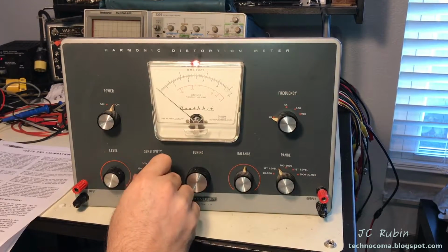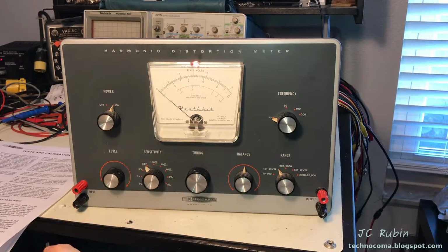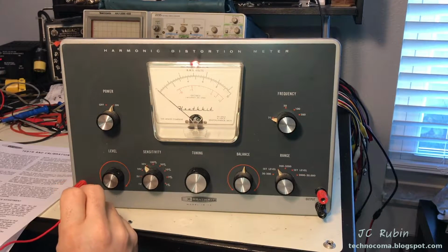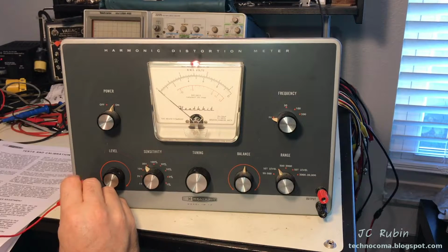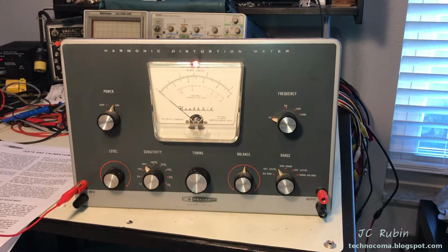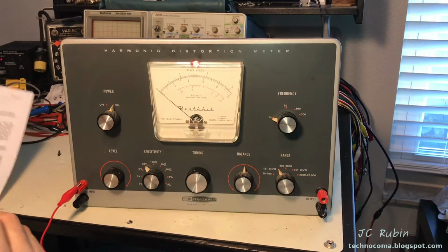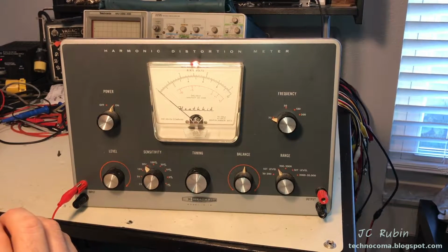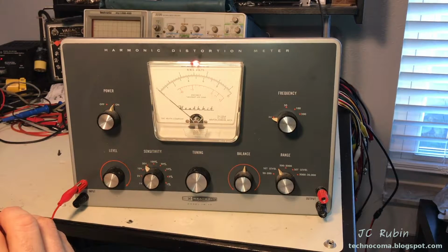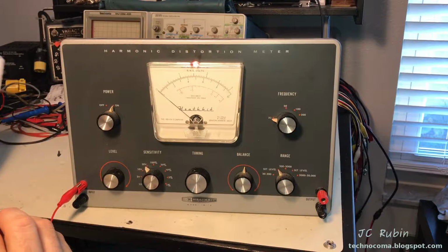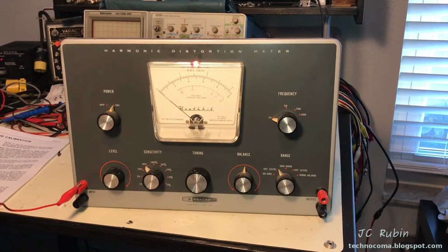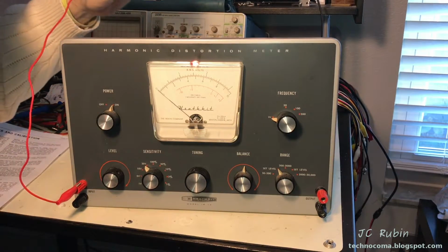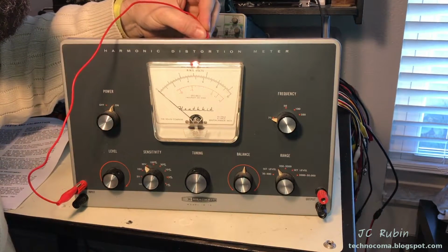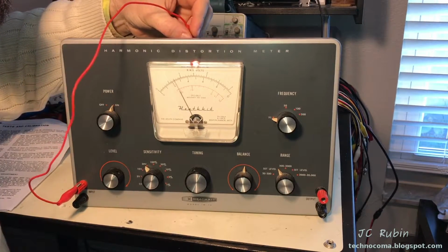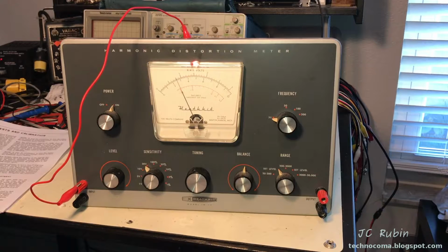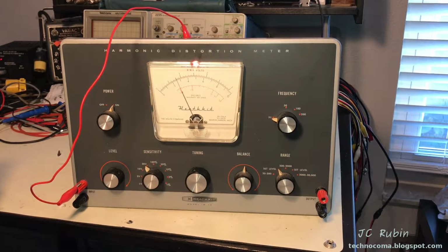So now it wants me to set the sensitivity to 30 volts and connect a piece of wire to the hot input binding post. I'll assume they're talking about that one right there, as it's the only input binding post. And then it says connect the other side of that wire to one side of the pilot lamp, whichever side gives an indication of deflection on the meter. Okay, fair enough. So I imagine we're going to be using this as a voltmeter to find out what the voltage is, right? And now we have a voltage right there. So we're using it as a voltmeter, right?